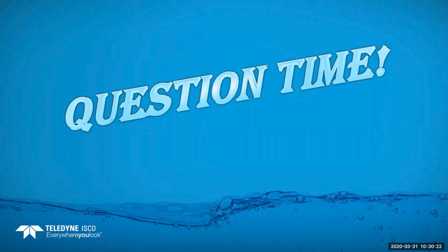Okay, we have a comment. Liquid level actuator sometimes acts like it is inside water because of some drops of water at the tip. Yeah, sometimes on the liquid level actuators, if you're getting drops of water, there's a rain shield that goes on those liquid level actuators that shields it and doesn't let rain get on there.